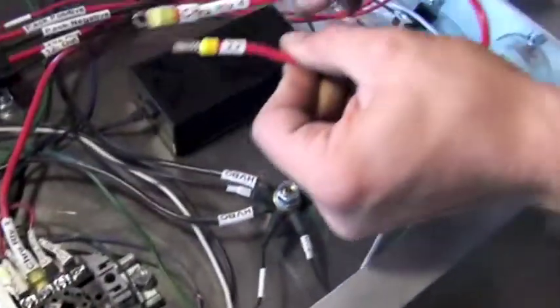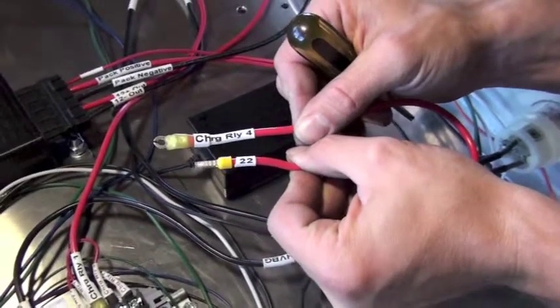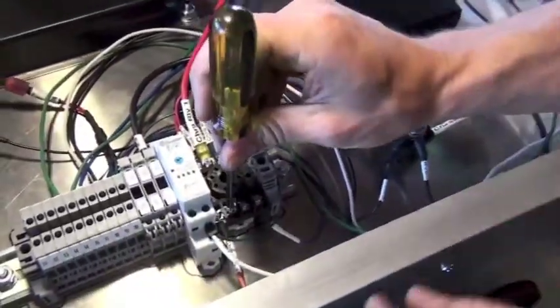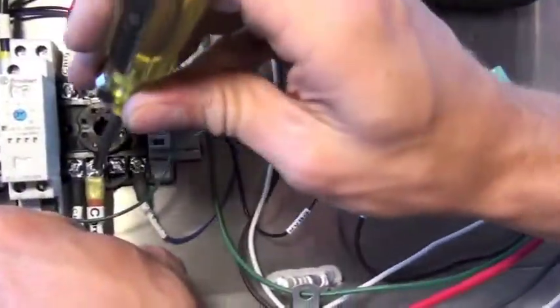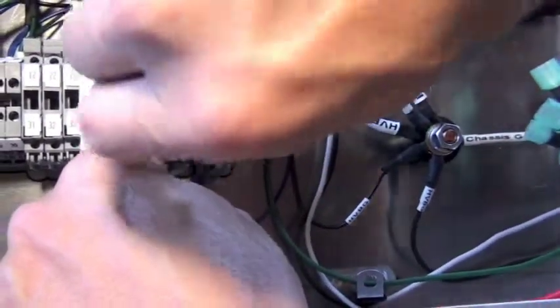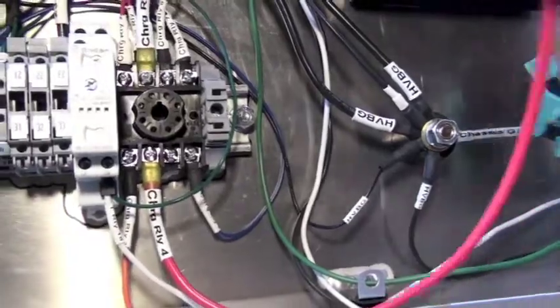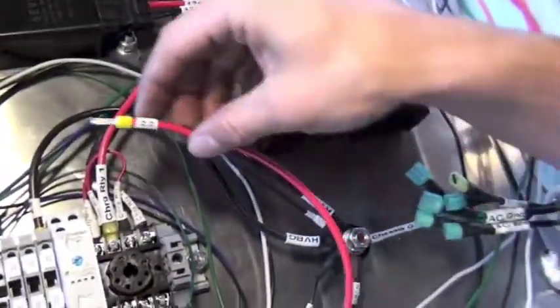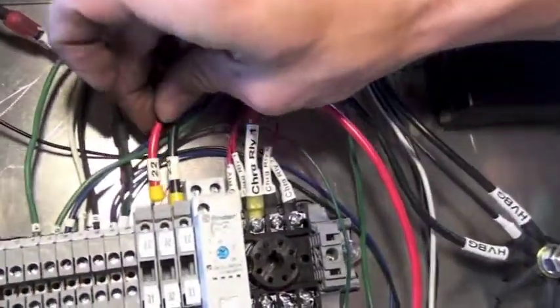We have a couple more on the other side, a couple more posts. One goes to charger relay position number 4. So we'll connect this connection down, and then the other end of this wire circles over to fused position number 22 on the DIN rail. Just as a note, we will have one open position on the charger relay. You can see it here. There's one connection that's not made on the charger relay of the 8. So we can loop that wire around and tighten it into place in position number 22.